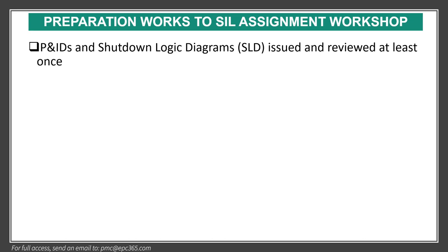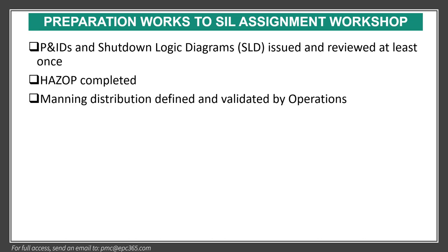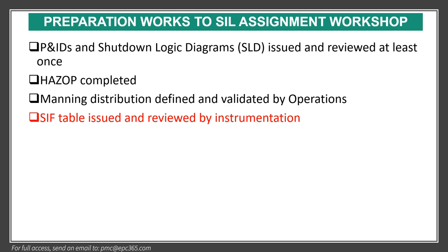To prepare the SIL assignment workshop, certain documentation must be ready. P&IDs should be ready, along with the shutdown logic diagram — which can also come from the cause and effect matrix. The HAZOP must be completed, and the manning distribution defined and validated by the operator. This is very important; that is why we need to have the fire zone defined. We also need to have a SIF table, a summary of the SIF table, which can come from HAZOP or the shutdown logic diagram.